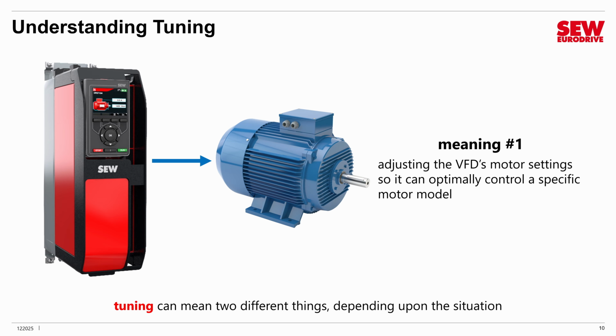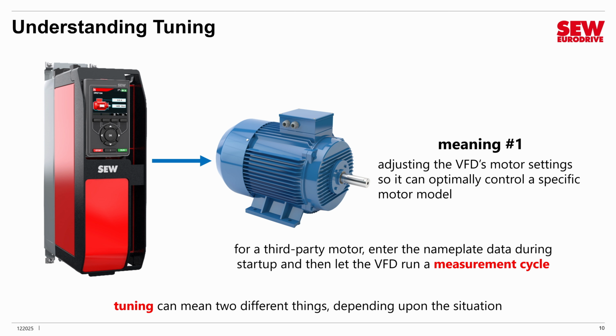Now, the first definition means adjusting the VFD's motor settings so it can optimally control a specific motor model. Notice I'm showing a generic third-party motor here, and there's a reason for that. When you're using third-party motors, you do need to tune them as part of the commissioning process, and that's because our VFDs don't know a whole lot about their electromechanical properties. So what you do is you enter the motor's nameplate information, and then you enter what's called a measurement cycle. What the VFD will do, it will run a small amount of current through the motor's windings. Sometimes you'll hear this kind of groaning noise from the motor, and the shaft may twitch a little bit. After a while, the VFD will say, okay, I've got the measurement. It'll set some parameters, and at this point, it can optimally control that motor. That is type 1 tuning.